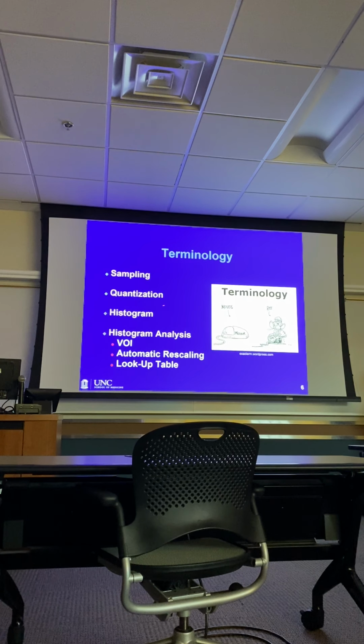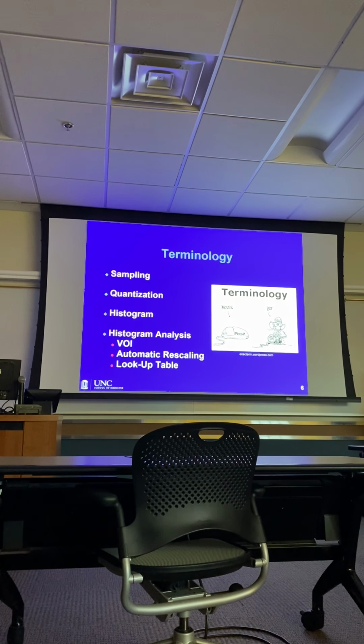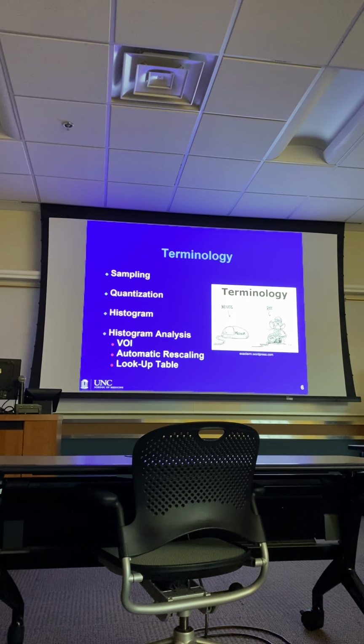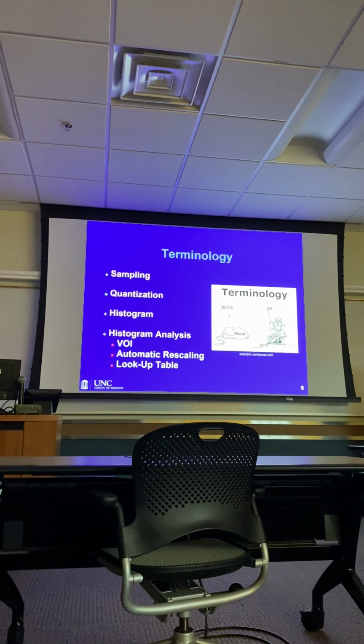And then the other thing the analog to digital converter does is quantization. It takes the pixel and assigns it a value. Think of the term quantity, so it's assigning a value. That value is based upon the bit depth, because the value assigned to each pixel can't exceed the number of values that the computer can assign it. But it's also based upon the intensity of the signal that's been received, how the x-rays interact inside the patient's body, which plays a role in the number assigned to the particular pixel.